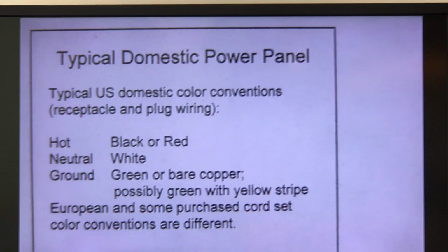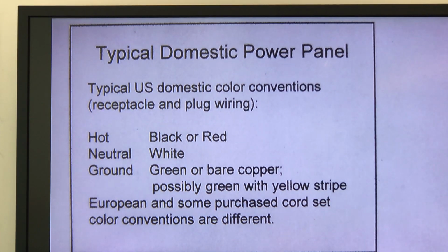Now, as we mentioned, that's the anatomy of the receptacle body. But let's talk about what's behind the receptacle. We're going to take a look at what constitutes a typical domestic power panel. And we're going to talk about the insulation color codes that are most commonly encountered. And then we'll build up the anatomy, if you'd like, of the electrical connections in the panel.